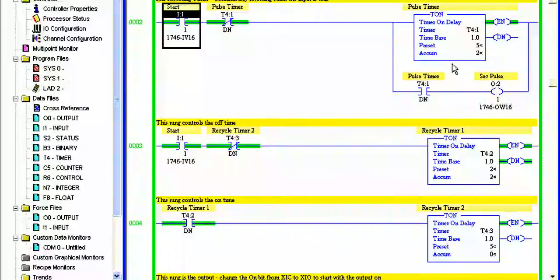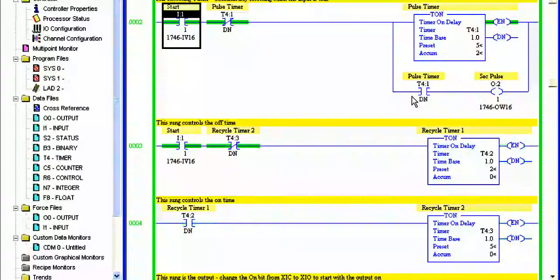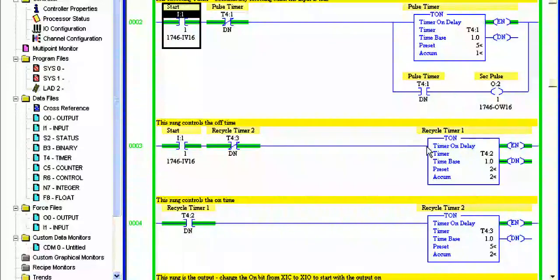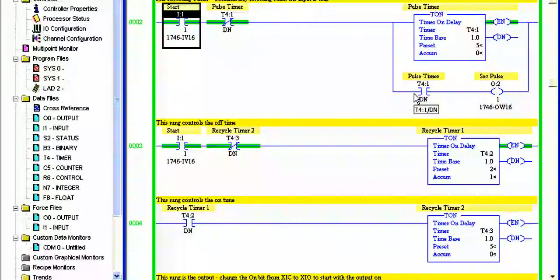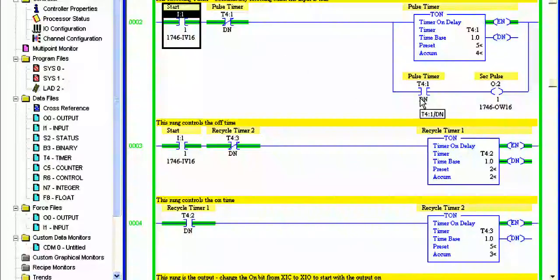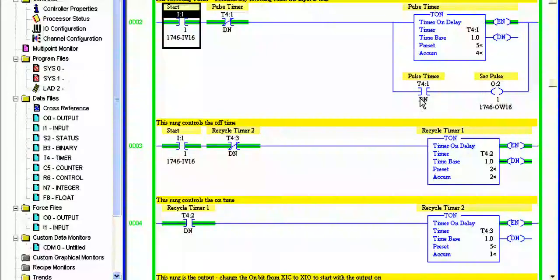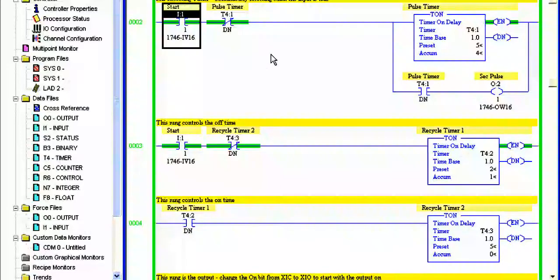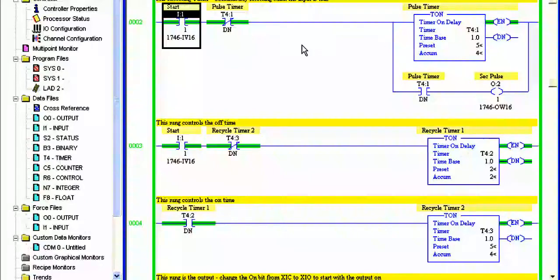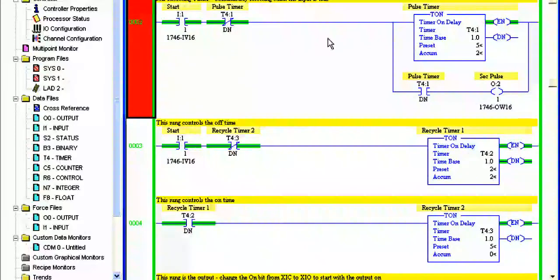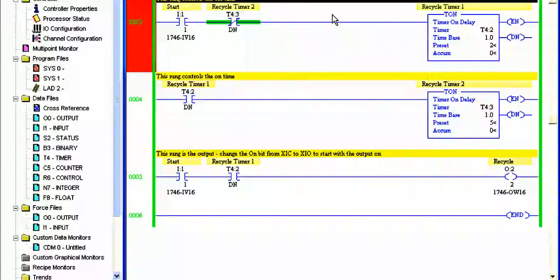So I'll right click here and give it a toggle and you'll see now that it's five seconds on and off. And you just notice then there's a bit of a toggle there. Don't take any notice of these circuits below, they're just affected by that input. But really we're looking at this rung here, just rung two. So you'll see every five seconds we've got a pulse. It's a one scan pulse but it is a regular time base. And you can of course adjust this to anything you want. So you can make a one second pulse or five second pulse. You can have less than a second if you want to change the time base. So that's a handy self resetting timer.